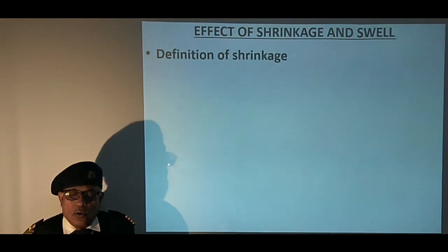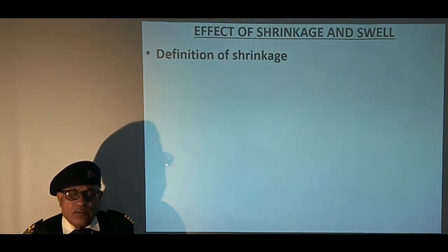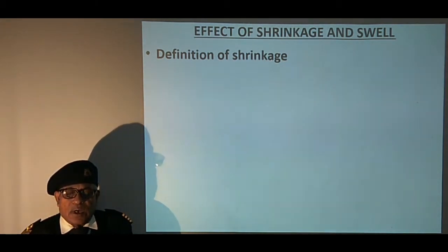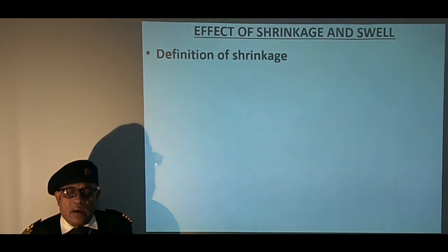When boiler load reduces suddenly, as in case of tripping of a steam turbine, steam pressure will rise, thereby causing the reduction of bubble formation, showing an apparent drop in water level, although the mass of water is actually increasing, and it is termed as shrinkage.